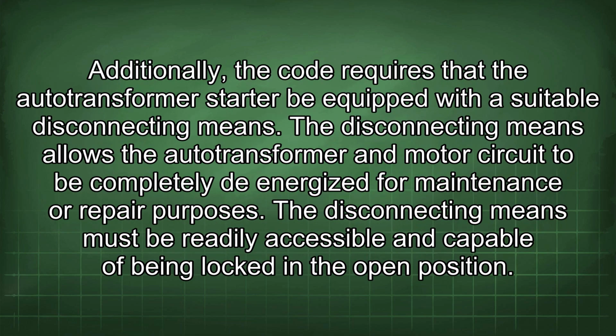Additionally, the code requires that the autotransformer starter be equipped with a suitable disconnecting means. The disconnecting means allows the autotransformer and motor circuit to be completely de-energized for maintenance or repair purposes. The disconnecting means must be readily accessible and capable of being locked in the open position.